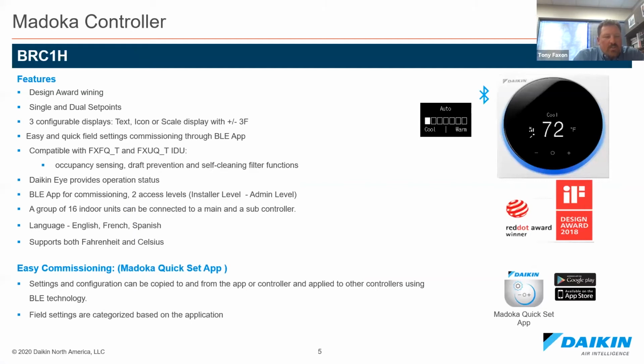This controller has been extremely popular throughout Europe and even won the Red Dot Design Award in 2018. It has a round black display against a white backdrop. There are 3 configurable display options. You've got text, icon, and there's a popular simple display with 3 temperature degree options up and down, but it doesn't show room set point or temperature. An LED shading system around the display called the Daikin Eye is standard, and it can glow red, blue, or green, showing the operational status. This option can also be dimmed or turned off if not desired.